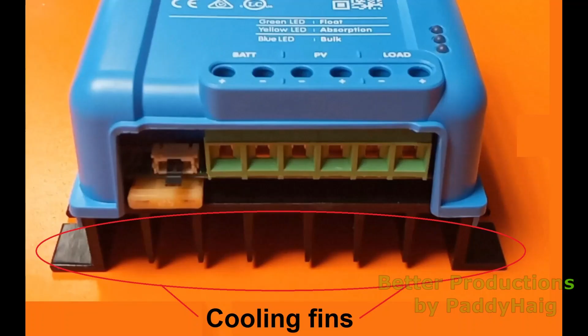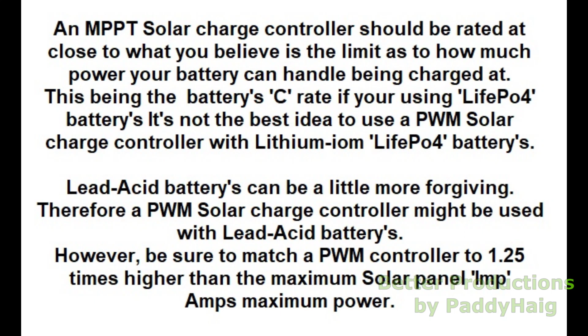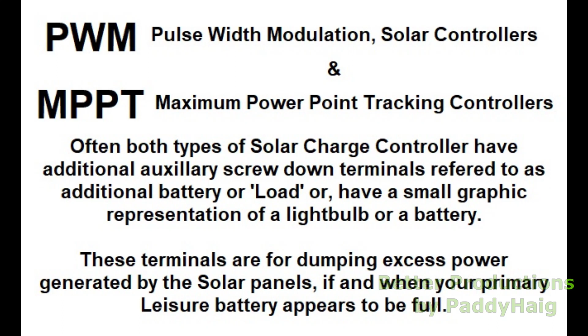If you're using a PWM solar controller, it's very important that it be rated at a higher amperage than your solar panel's total output, as a PWM controller doesn't handle heat well and can be a fire hazard. Although MPPT controllers can handle some excess amperage, it's still best to get one rated close to your panel's maximum output, if not a little higher.